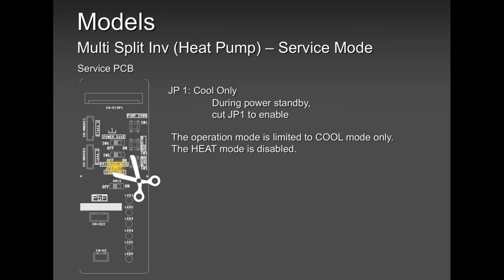Then some guys will call me, especially in some warmer regions closer to Seattle, they will say, Paul, I want to use this heat pump only for cooling. I have my own boiler, I have my own source of heat. I don't need this heat pump for heating. So all you tell them is cut that jumper. There is a jumper on the service PCB. You cut it off, you are in cool mode only. And sometime down the road, if they want their heat pump back, just take a solder and solder it. And you're back again into heat pump mode.